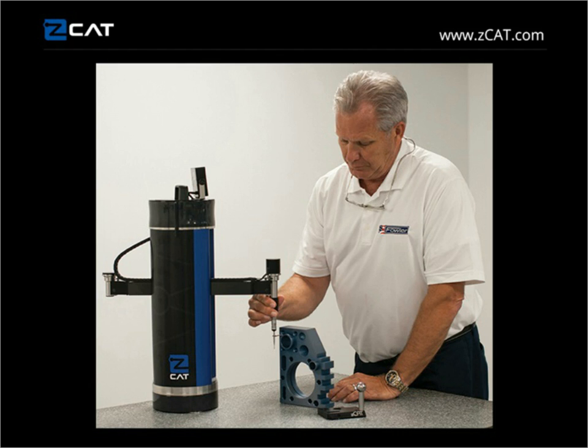But what we're coming up with accuracies are, we'll state a formula based on how much measuring range you're going to use, but if you really want to get into volumetric accuracies that they state in coordinate measure machines, we're getting around 8 to 9 microns accuracies. With the zCAT, we're getting repeatability at 3 to 4 microns, and we have full intentions, and we truly believe we'll even be able to get better than that. But here you can see how an operator would use this gauge, and you can also kind of get an idea the size of the gauge based on the operator.